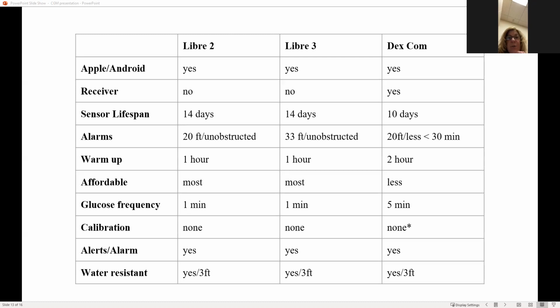Alarms, this is something that's changed through the Libre 3 that has the most amount of distance that you can be away from your phone. So the other two are 20 feet, and Libre says unobstructed. So unobstructed to them is leaving the room or having a wall between you, or likely going upstairs to downstairs. As long as it's unobstructed and you're within 20 feet, the Libre 2 will function. Libre 3 is within 33 feet unobstructed. And Dexcom's a little bit different. Theirs is within 20 feet in less than 30 minutes. So as long as you could go upstairs or downstairs, but you need to get back to your phone or receiver within 30 minutes in order to not lose waveform and alarms.